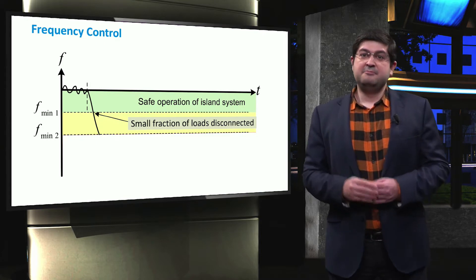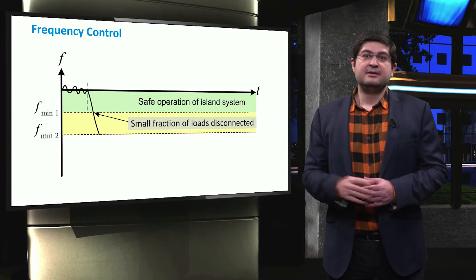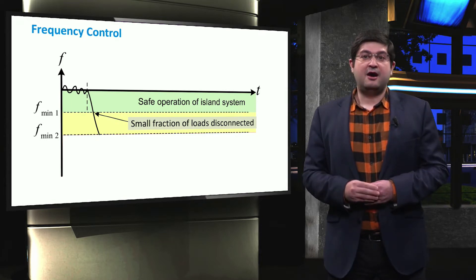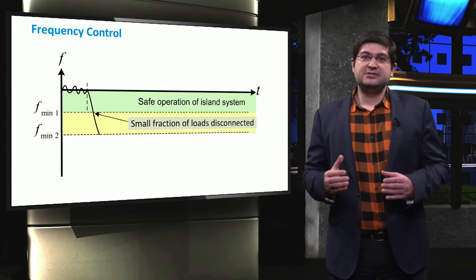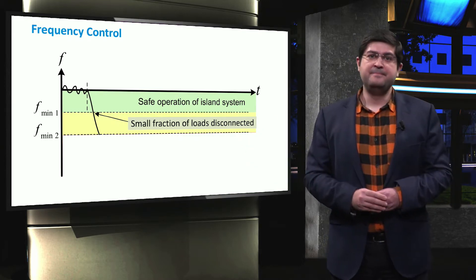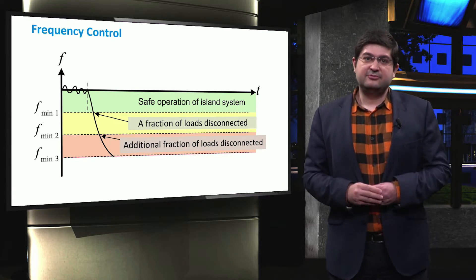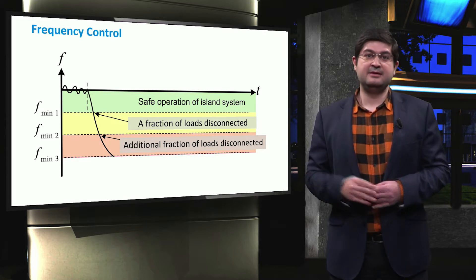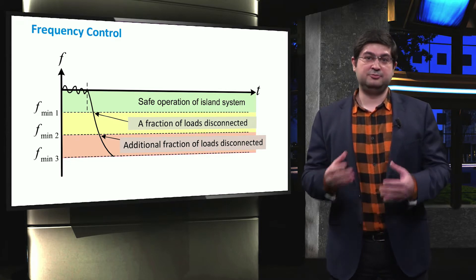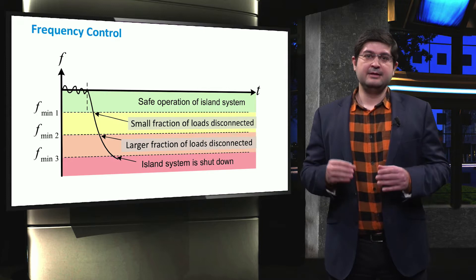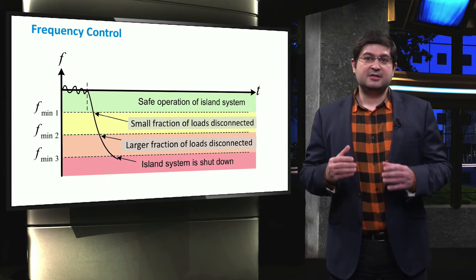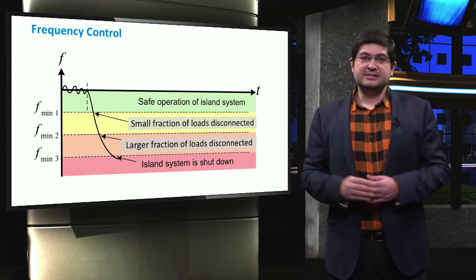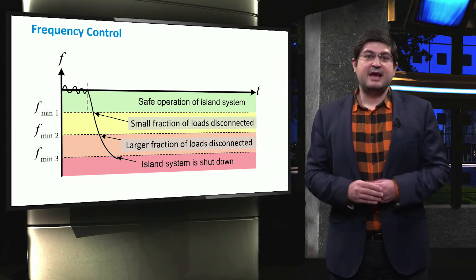However, if the frequency decreases below a certain limit, fmin1, then a fraction of the loads are to be shed to control the frequency. This is the first threshold for the implementation of under-frequency load-shedding. According to various standards, this fraction of the load might vary from 5% to 25%. If the first load-shedding action would not be effective enough to stop the frequency drop, then another load-shedding step might be applied. When the frequency decreases below the second limit, fmin2, then an additional portion of the loads are to be shed. If the under-frequency load-shedding schemes do not stop the frequency drop, then the islanded microgrid might be shut down by the under-frequency protection relays. fmin3 shows the minimum limit at which the microgrid is shut down.